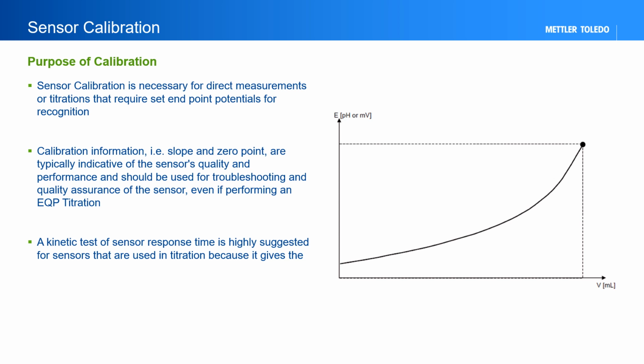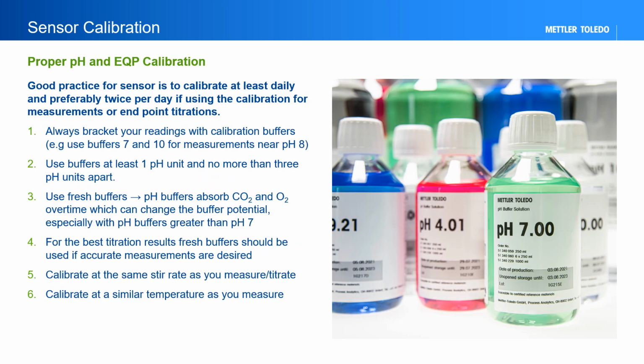A kinetic test can also be used to test the ability of your sensor to respond to potential or concentration changes fast enough for it to be suitable for your titration method. A good practice for sensor calibration is to calibrate at least daily and preferably twice per day if using the calibration data for measurements or endpoint titrations.